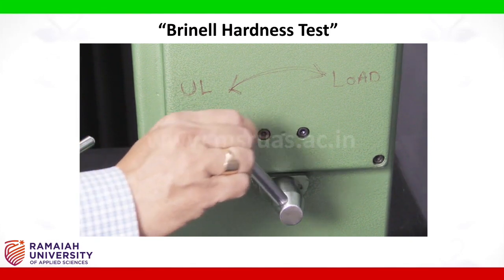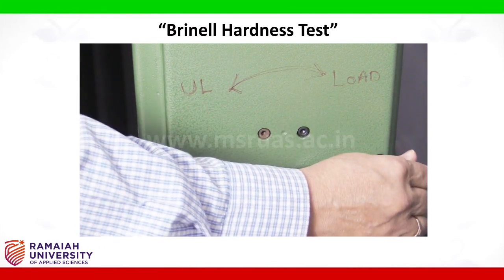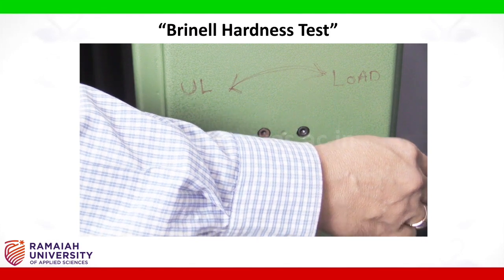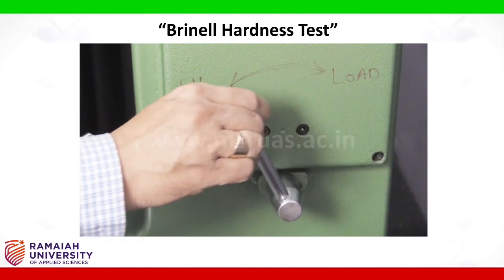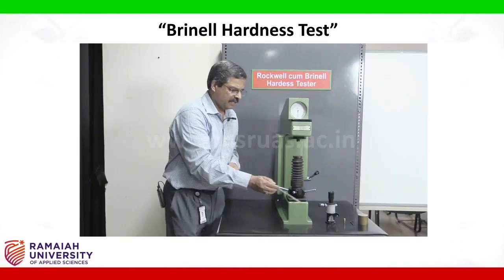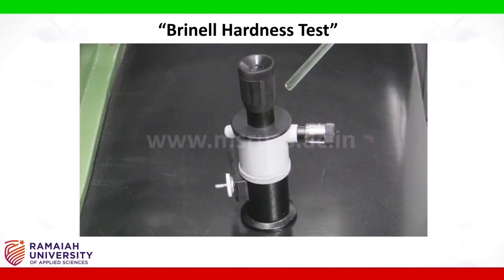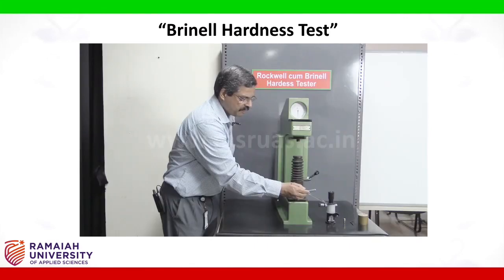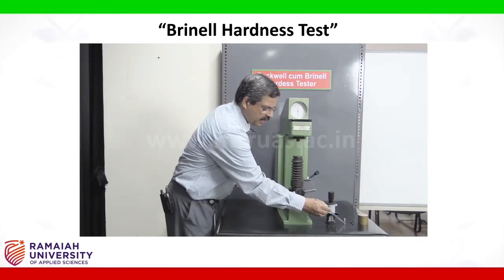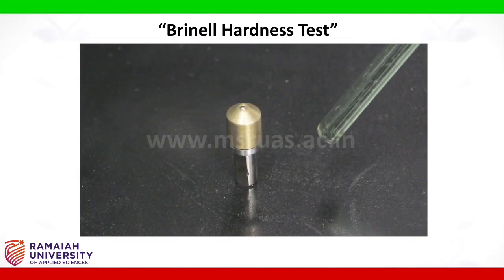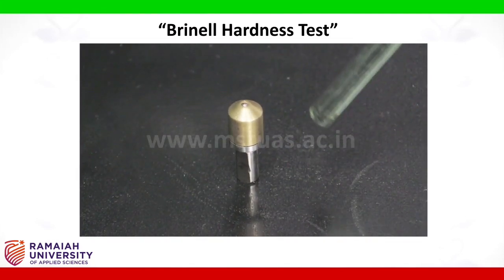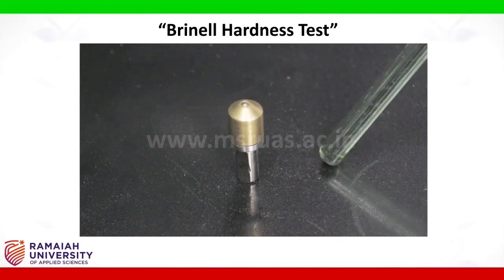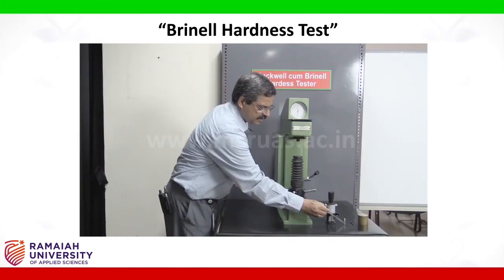When we turn the lever to this side, we apply the load, and then when we take it back, we remove the applied load. The Brinell microscope. This is the Brinell microscope which is used to measure the indentation diameter. The indenter. This is a 2.5 mm ball indenter which we will be using for testing the specimen brass.